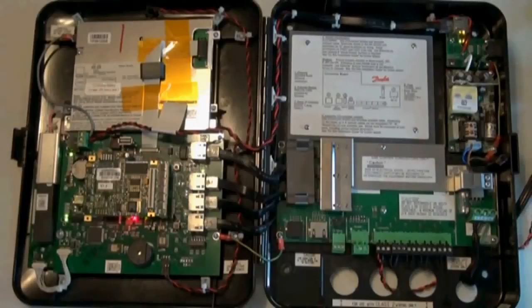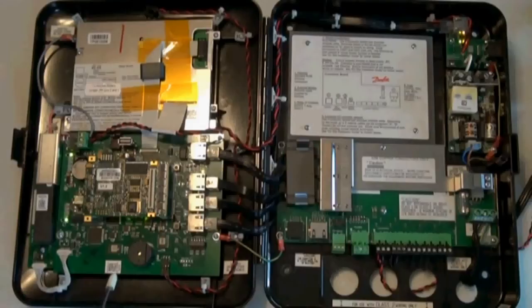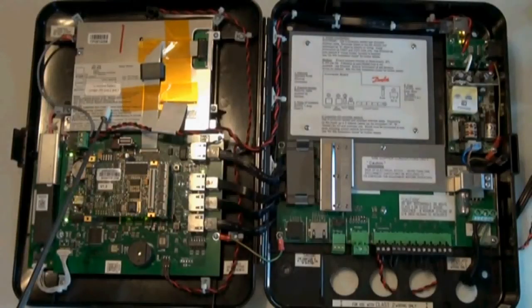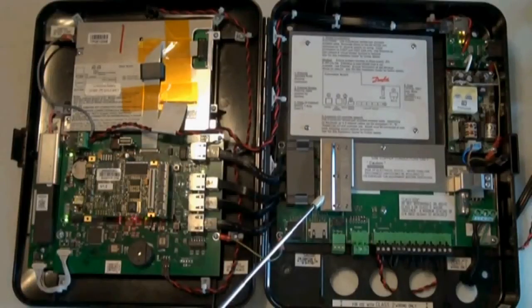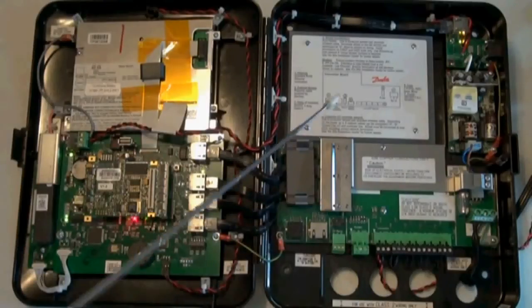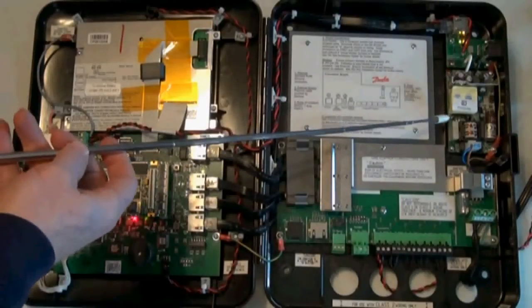Here's an overview of the inside of the Danfoss AK2-55. Here you'll find we have the baseboard and CPU board combination. The CPU is the smaller board and contains a sticker with the MAC address of the controller. This board is the inverter for the backlit display, and the display is found here. On this side we find the input board where inputs come into the unit. Also, communication connections are made. On this side we have the power supply.